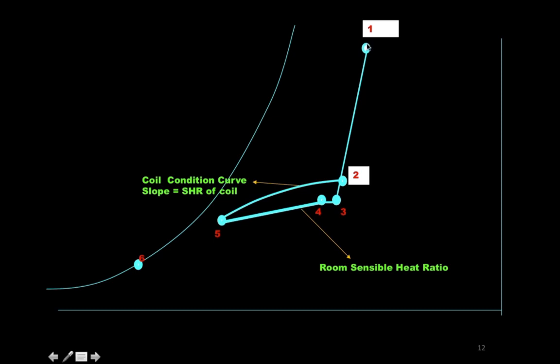We mix with the outside air, which is hot and humid. And 2 is the entering condition of the cooling coil. And if it goes down to the off coil condition, which is 5, this is the slope. 4 to 5 is the room sensible heat ratio line I was talking about. And in this particular slide, the slope of the coil is compatible, so everything is fine.